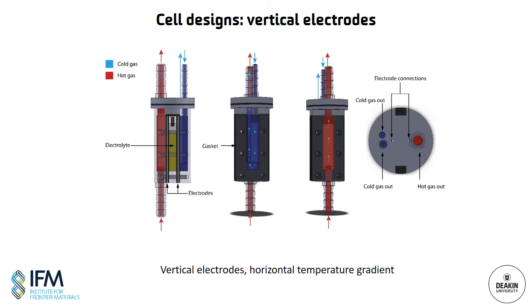So they involve the use of two gas lines to control the temperatures on each side of the cell independently. So the hot and cold gases flow in and out through the exterior of the cell, and they flow past the exterior sides of the electrodes, which are just platinum strips, and they're held in place by rubber gaskets. The cells themselves are made from the PEEK polymer, which is unreactive and fairly easy to machine, and it's commonly used for cells for in situ NMR and MRI experiments. Then we have obviously wire connections to the platinum electrodes that allows us to connect these to an external potentiostat. And the hot and cold gas supplies are coming from two BCU chiller units. So this design allows the temperatures of each electrode to be controlled independently, and it allows us to establish a stable and controllable temperature gradient across the electrolyte.